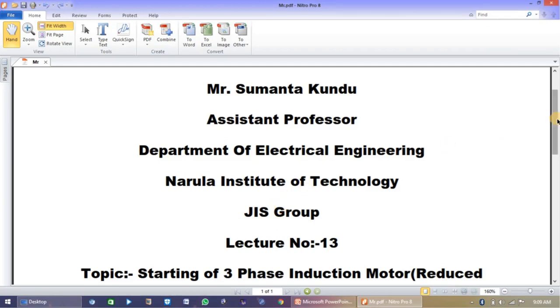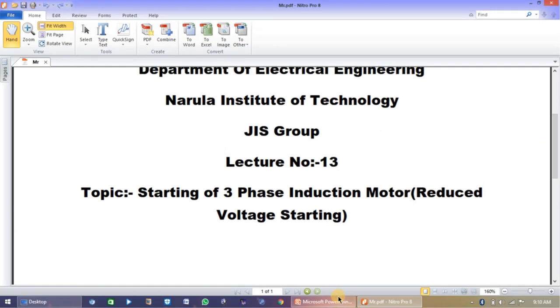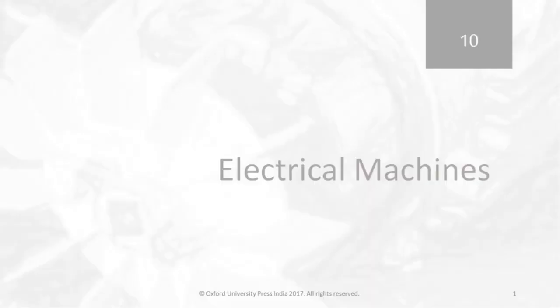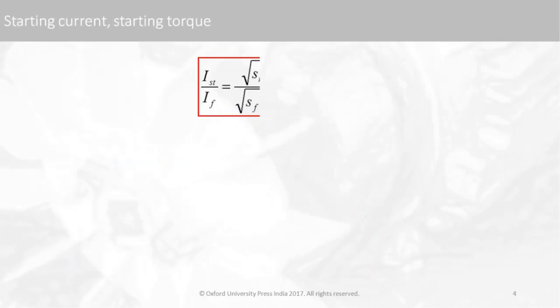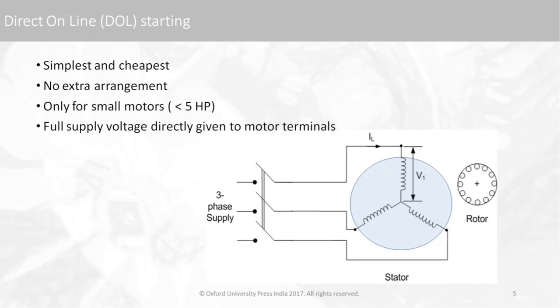We are going to start Lecture 13 on the starting of three-phase induction motors and we will discuss the reduced voltage technique. When we discussed starting of three-phase induction motors, we first discussed the DOL starting method. During that lecture we mentioned that the starting current of a three-phase induction motor is very high — almost five to six times the full load current. My goal is to reduce this starting current so that it cannot damage the motor windings.